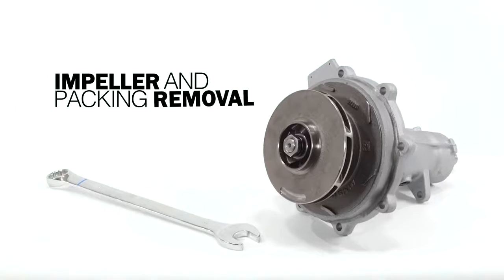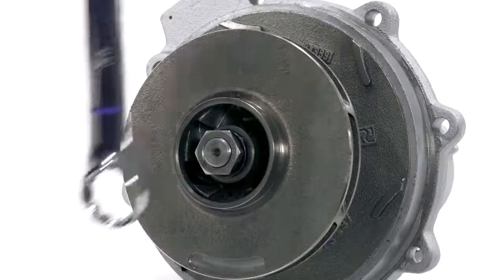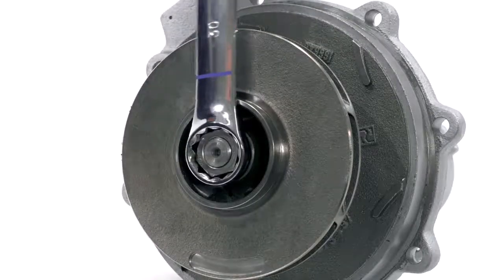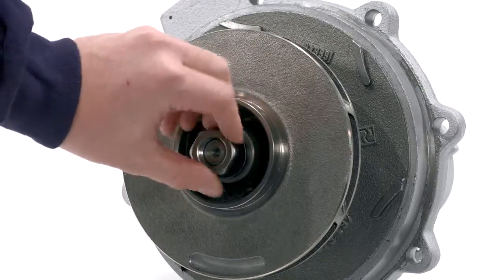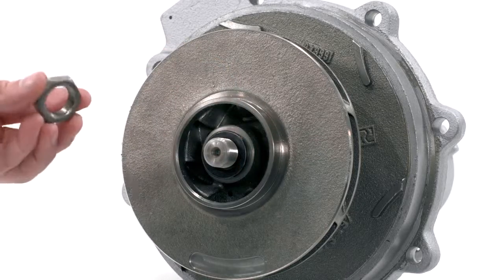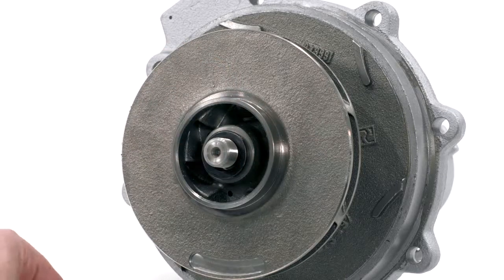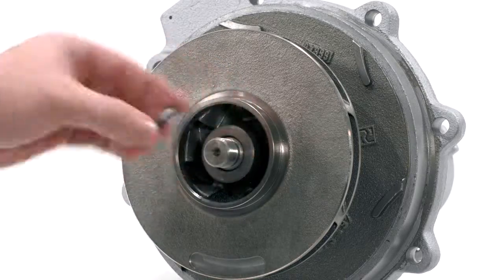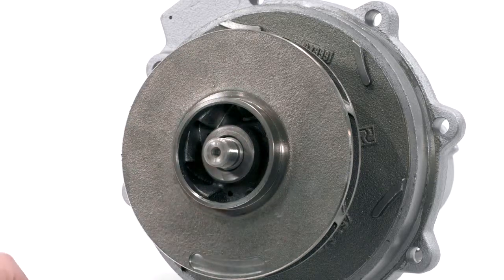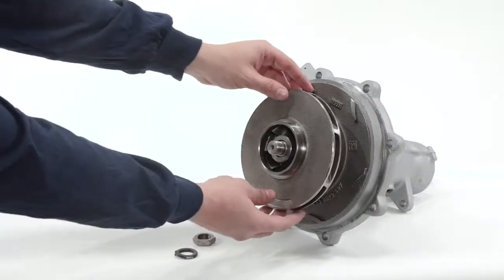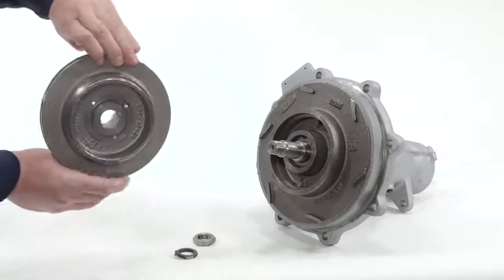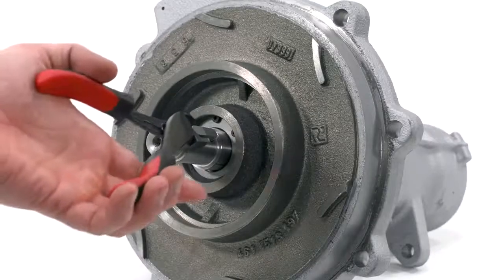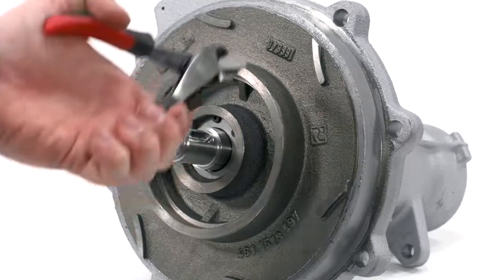Impeller and packing removal: Remove the impeller nut and lock washer by unscrewing it off the pump shaft with a 30mm wrench. You should now be able to slide the impeller off the shaft. Remove the impeller key from the shaft using a pair of side cutters.